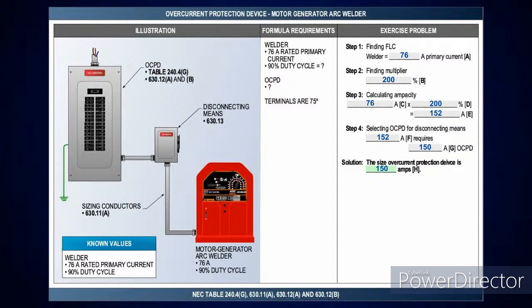Now, this is what I'm going to use with the duty cycle if I'm going to do the conductor. But if I'm not going to do the conductor, I can just look at the welders in 630.12(A) and take it at 200%. Okay, so I showed you 2 ways here to check and size the overcurrent protection device. I'm going to take the 76 amps at 200%, that gives me 152 amps. I look at table 240.6(A) for my standard ampere ratings. The next size below that is a 150 amp overcurrent protection device.